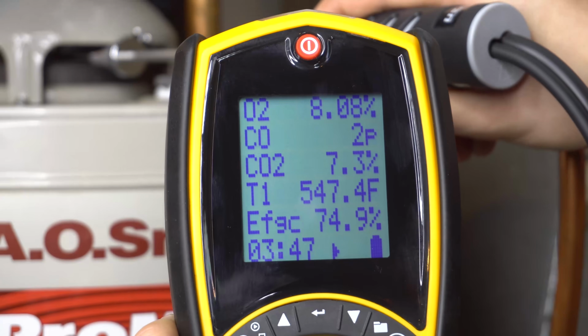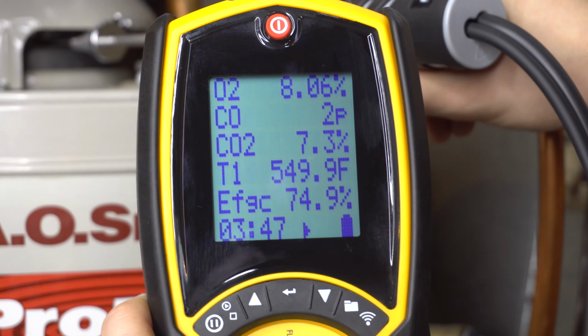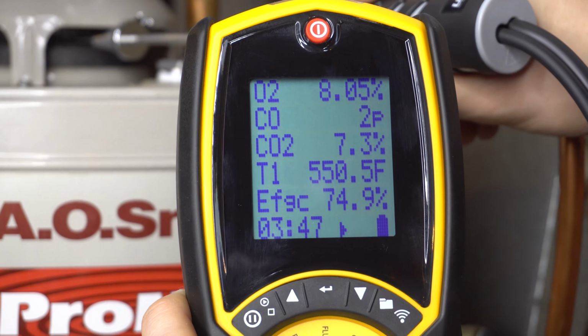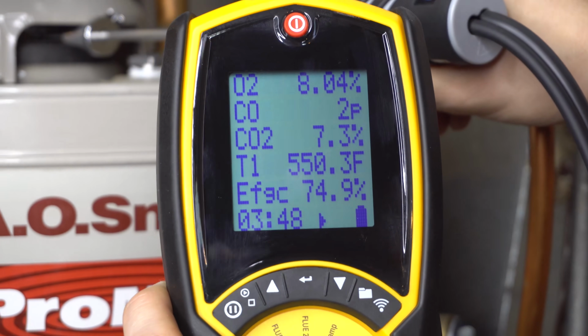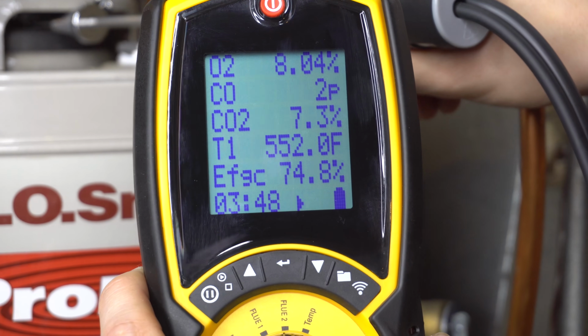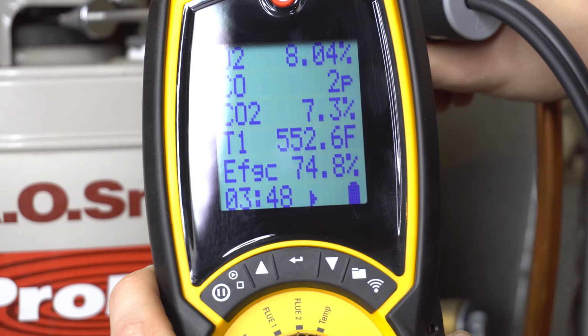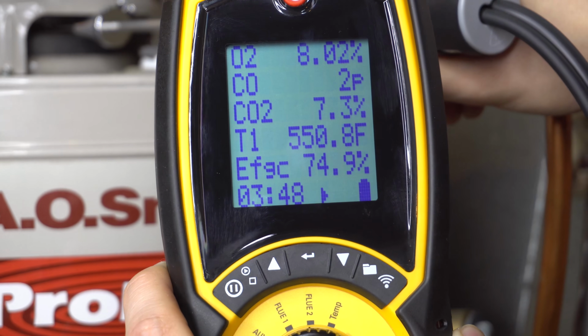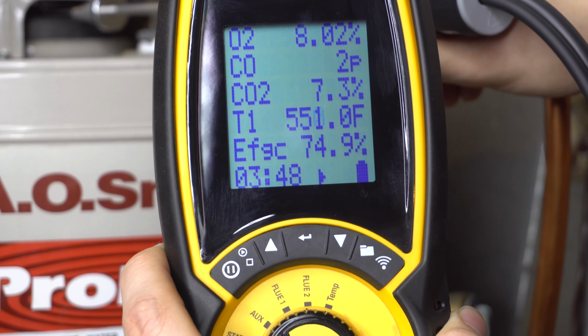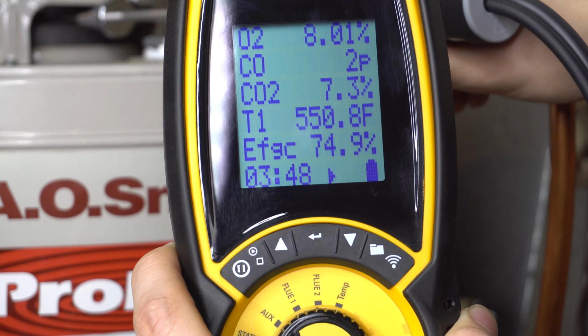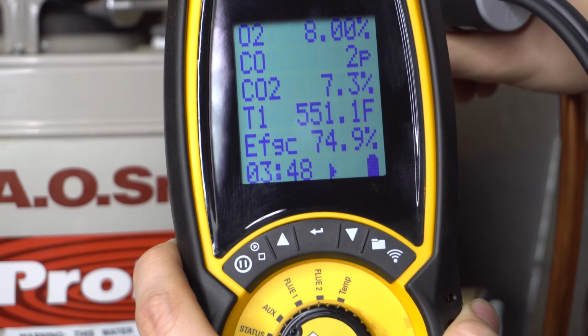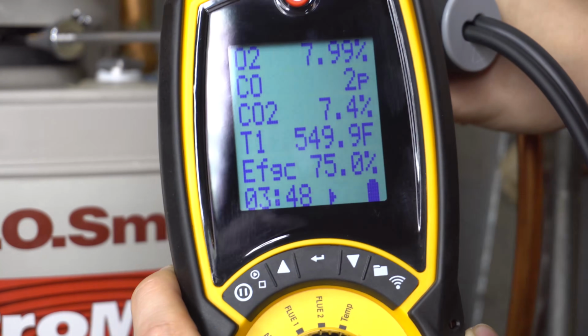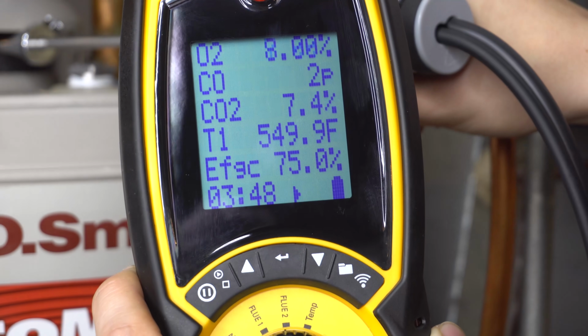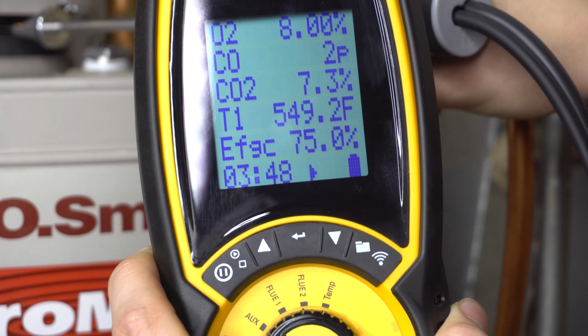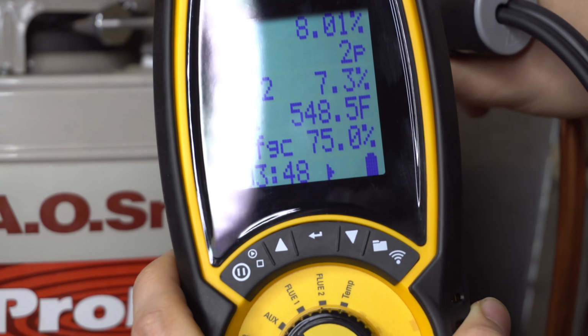So my numbers are pretty much stabilized, though they're still fluctuating a little bit. Oxygen is at 8%, carbon monoxide 2 parts per million, carbon dioxide 7.3, and the stack temperature is at 550 degrees, which is pretty high, but it is normal for an atmospheric draft furnace or water heater, which is typically somewhere between 500 and 600 degrees. And the efficiency is not bad either. It's at 75%.